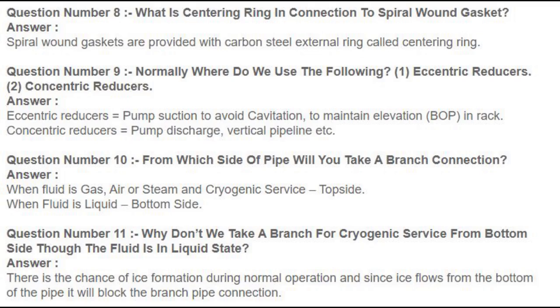Question number 10: From which side of pipe will you take a branch connection? Answer: When the fluid is gas, air, steam, or cryogenic service — from the top side. When the fluid is liquid — from the bottom side. Question number 11: Why don't we take a branch for cryogenic service from the bottom side though the fluid is in liquid state? Answer: There is a chance of ice formation during normal operation and since ice flows from the bottom of the pipe, it will block the branch pipe connection.